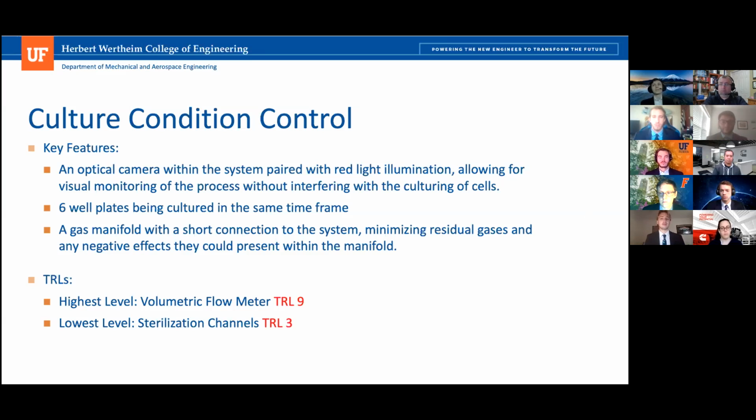We have 6 that could be going simultaneously. And then I mentioned the gas manifold. One important thing to note about it, which is mentioned here, is that it's very close to the system, and that gets rid of the worry of residual gas being leaked or residual gas going inside the system that you didn't want in the first place. The proximity of the manifold to the system gets rid of the worries of that.